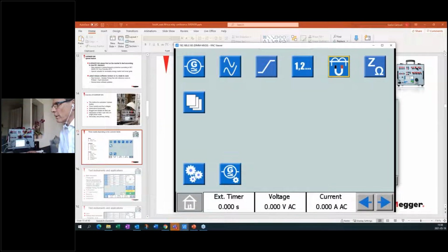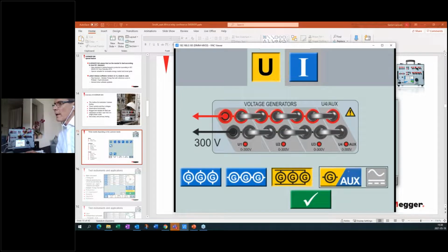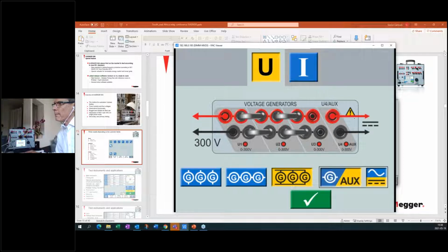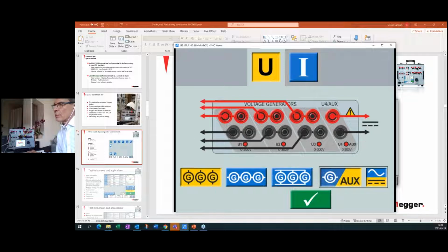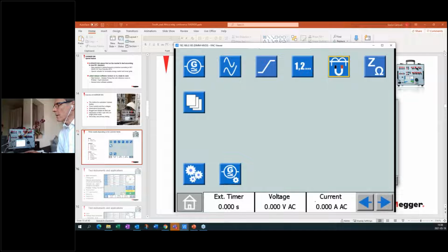I need to reconfigure the generators. So I go here to do the generator configuration. I need to power up. I have a protection on this side. I need to power up this protection, and I will use the U4 to make the power up. And I would like to have a DC power voltage, and also I put the other voltage output in individual mode. So I just set it like this and say okay.